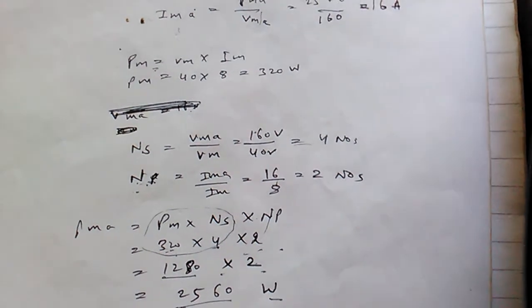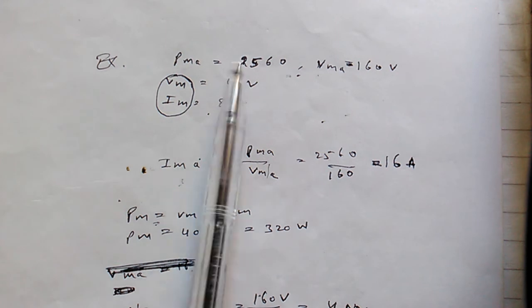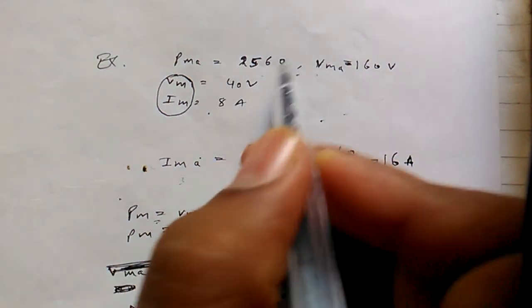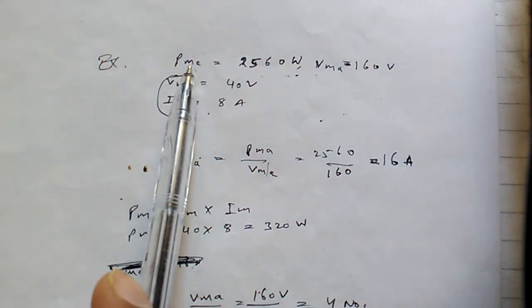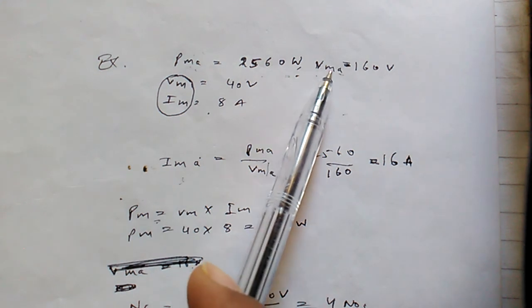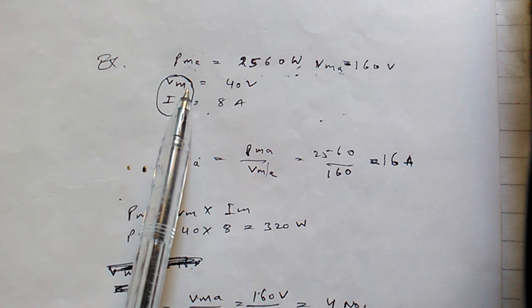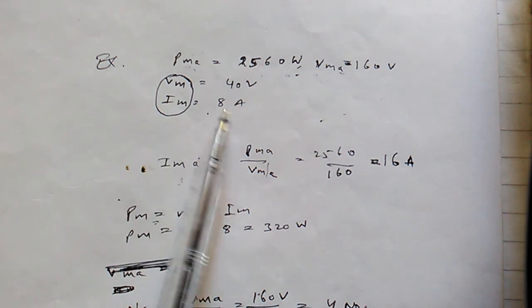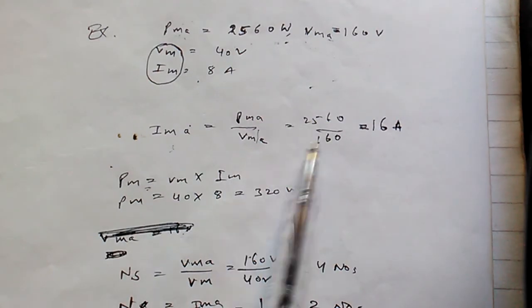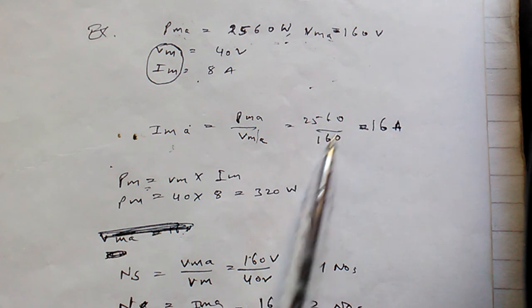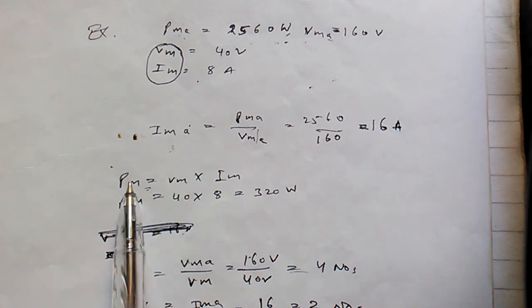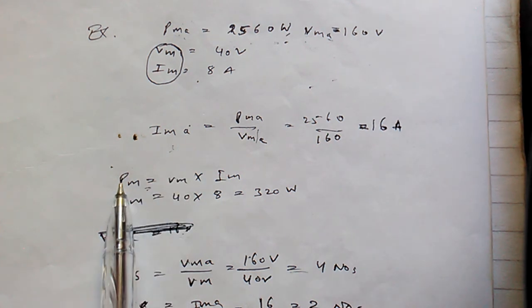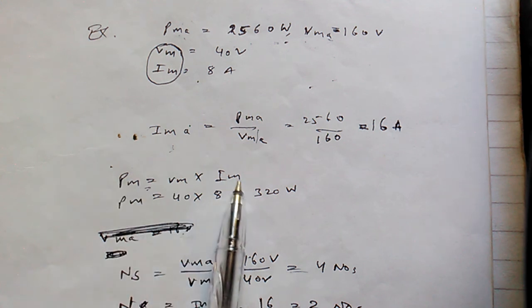Take an example: the array power at maximum power point (Pma) is 2560 watts, and the array voltage at maximum power point (Vma) is 160 volts. Module parameters are Vm = 40 volts and Im = 8 ampere. Using the formula Ima = Pma / Vma = 2560 / 160 = 16 ampere array current.